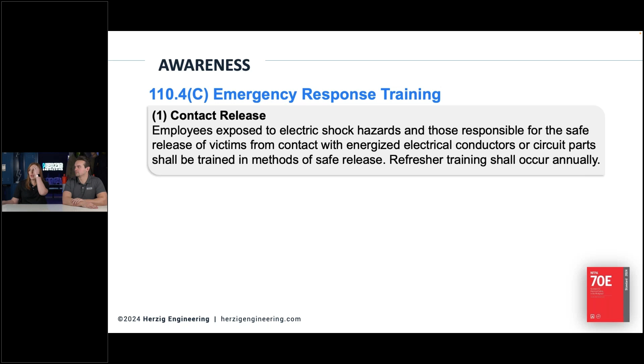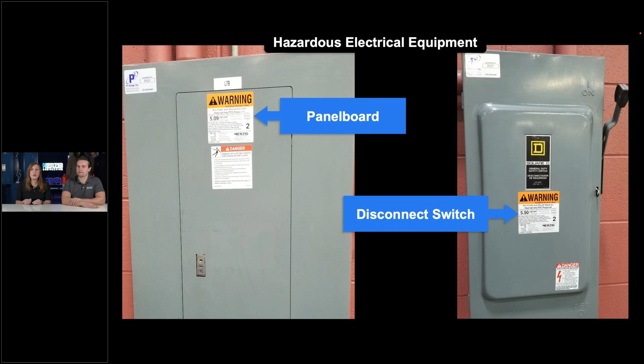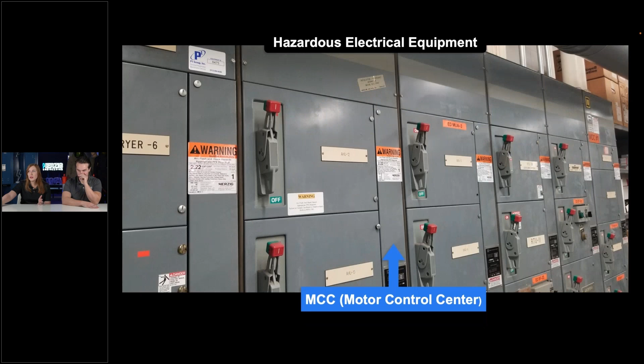Other things - there's electrical hazards in the enclosures themselves. Unqualified personnel should not be opening and accessing electrical equipment like this: panel boards, disconnects, certainly not switchboards or switchgear or motor control centers, right? Overhead bus duct, all that stuff, it should be a no-go zone.